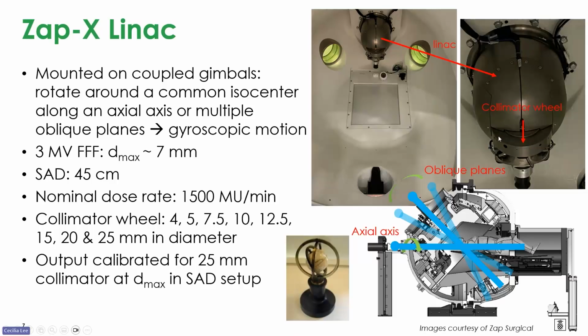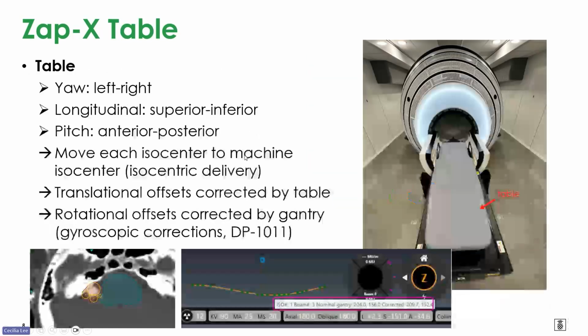Underneath the LINAC, there is a collimator, and it has 8 different circular openings from 4 millimeters to 25 millimeters in diameter. It rotates and then the center of the collimator aligns to the machine isocenter. And then the output is calibrated in an SAD setup at Dmax using the 25 millimeter collimator.